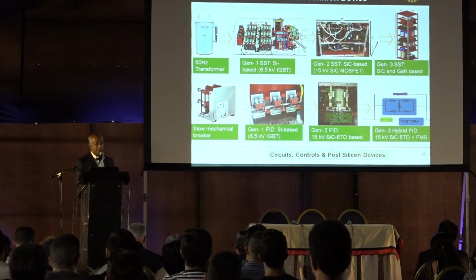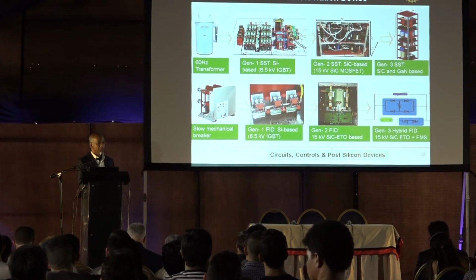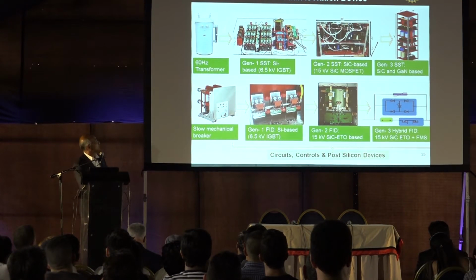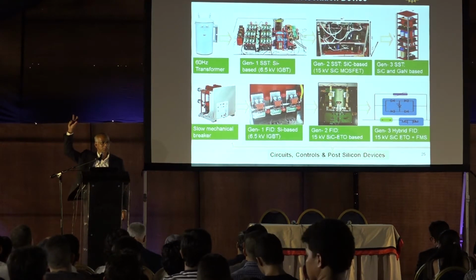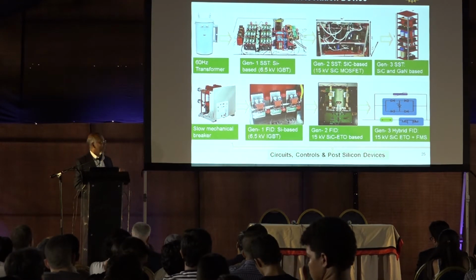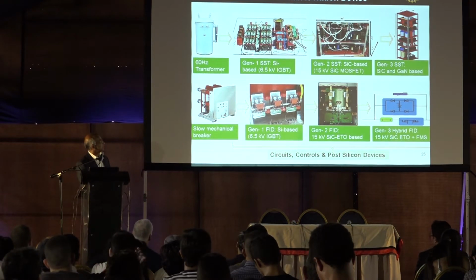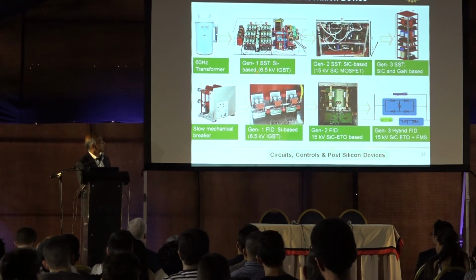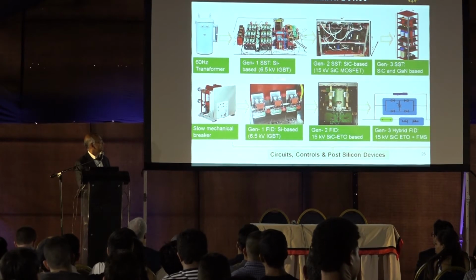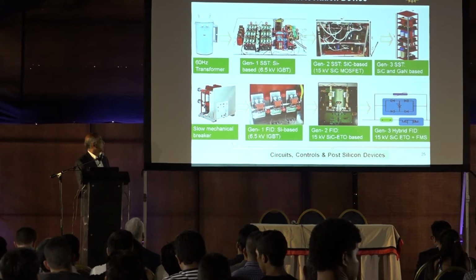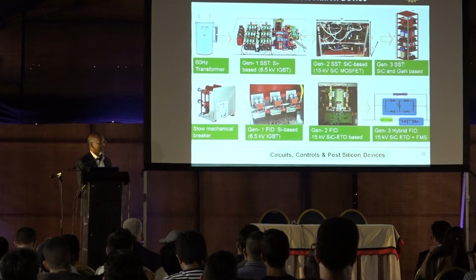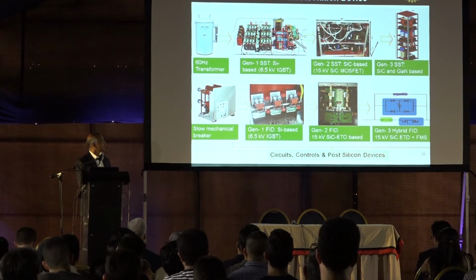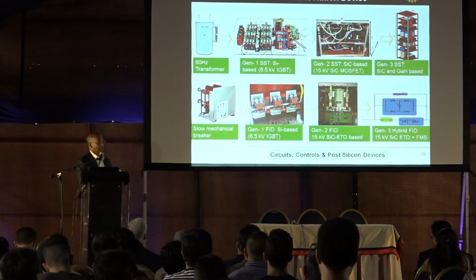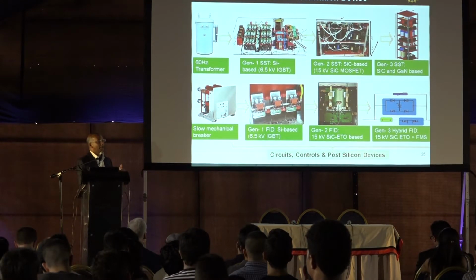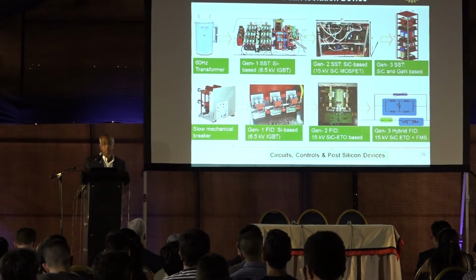This is a picture showing what we are developing and what we are trying to replace - this typical distribution transformer that you may have seen on pole tops. We're gradually reducing the size of these power electronics-based transformers from generation 1 to generation 3, and similarly trying to replace those mechanical slow circuit breakers with electronic plus electromechanical hybrid type circuit breakers.